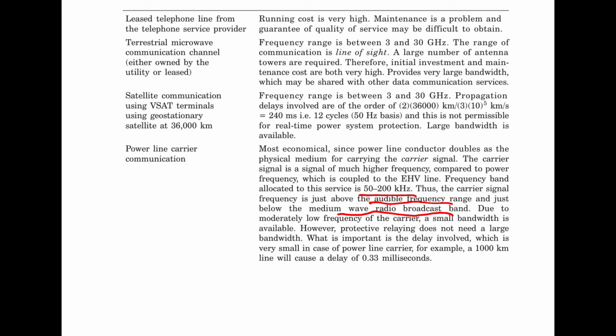Due to the moderately low frequency of the carrier, a small bandwidth is available. However, protective relaying does not need a large bandwidth. What is important is the delay involved, which is very small in the case of power line carrier. For a 1000 kilometer line, it will cause a delay of 0.33 milliseconds. So power line carrier communication is the most economical, and the carrier signal is a signal of much higher frequency compared to the power frequency, coupled with the EHV line.